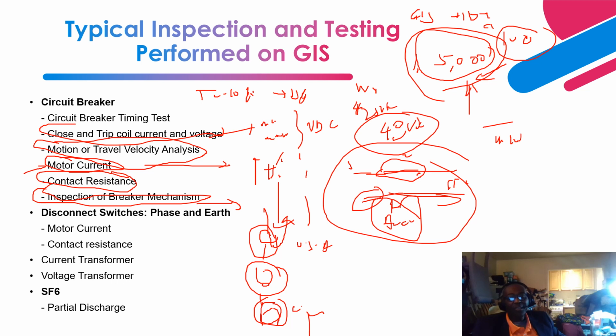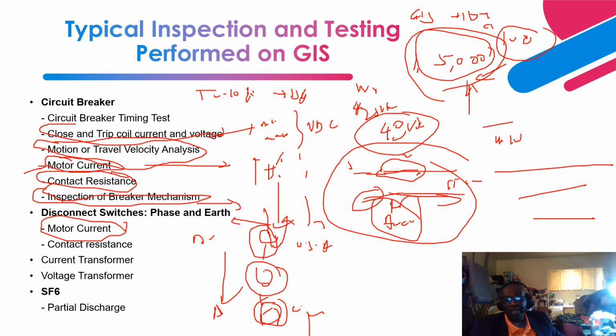Then you have an earth switch, so that is when you ground the bay to basically mitigate other stray capacitive charges that might be floating around on the GIS bay. So there are motors that operate these disconnect switches that are on this side of the circuit breaker. So this is the line side. Similarly, for the bus side, we have disconnect switches, and there are motors that operate them. Same applies to the earth switches. There are motors that operate. So they perform motor current testing, basically how much current it is drawing.